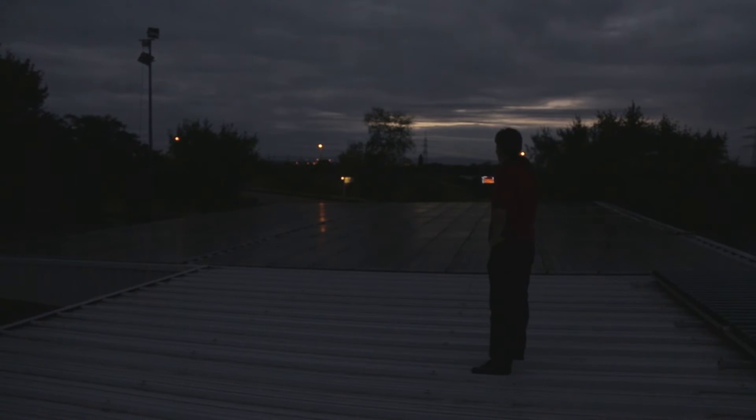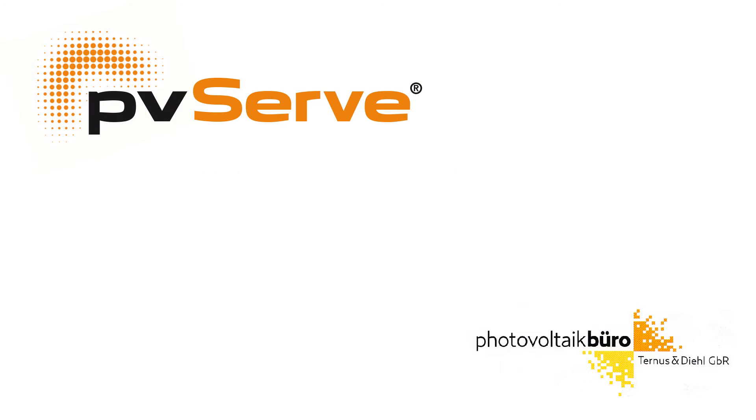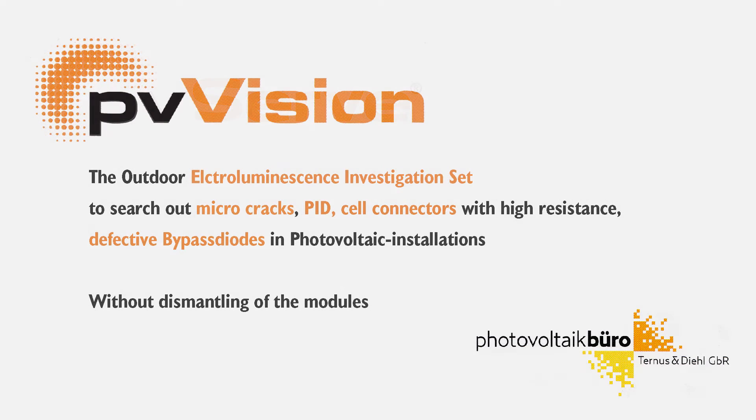This method is used to find how strings are arranged on a roof if there is no documentation. It can also be used to detect defective bypass diodes, hot spots, and cell connections with great resistance, without a lot of sunlight, and even at night.